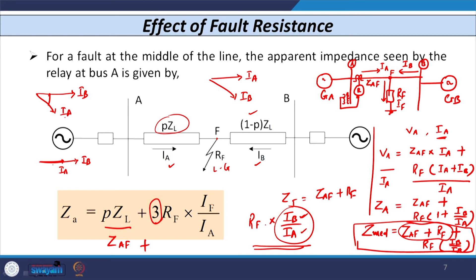So, because of the involvement of RF, only the real part of the measured impedance changes, but IB and IA are not in phase. It may be possible that the voltage or angle at bus A and bus B are different. So, IB may lead IA by some angle, or IB may lag IA by some angle, depending upon in which direction power flows, whether it is from A to B or from B to A in the pre-fault condition. So, depending upon the phase shift between the two currents IB and IA, the relay may overreach or underreach.